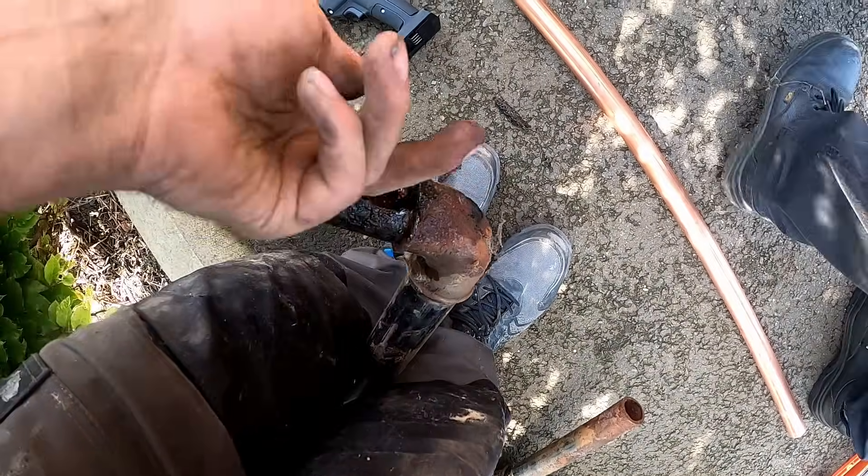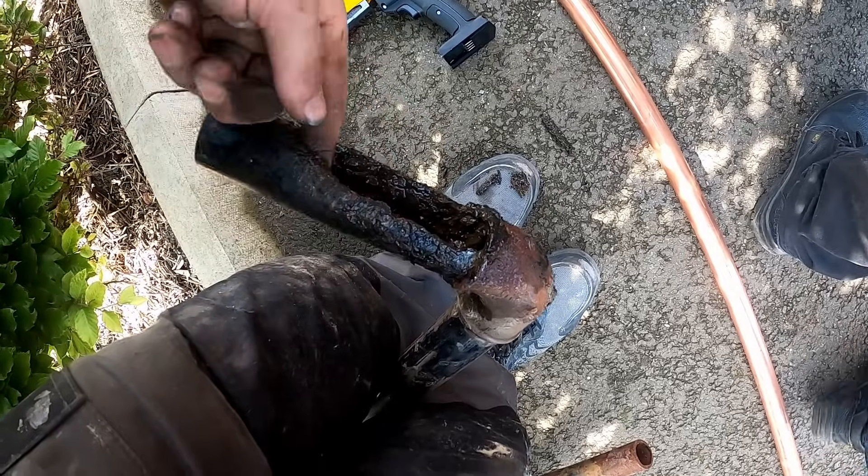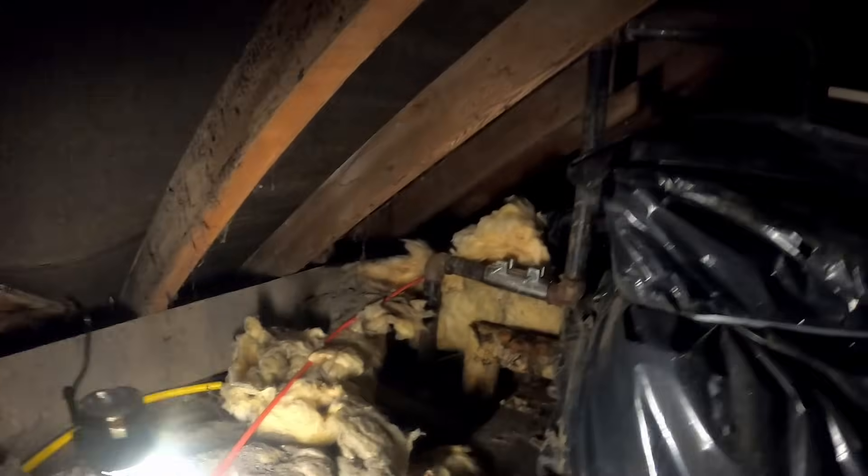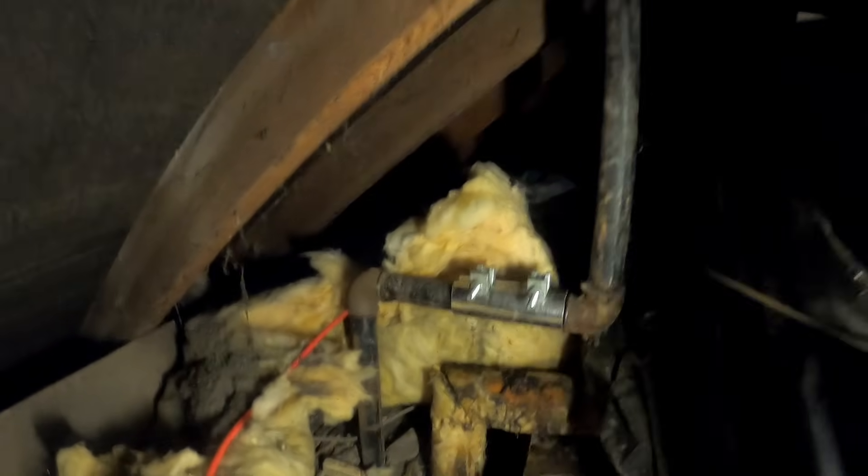On a scale of 1 to 10, I would say that was knackered. Look at that, it's completely gone. So I've been called to this job, right in the corner of an attic. That vent pipe coming over the top of this tank - this is a heating tank - it's corroded through.